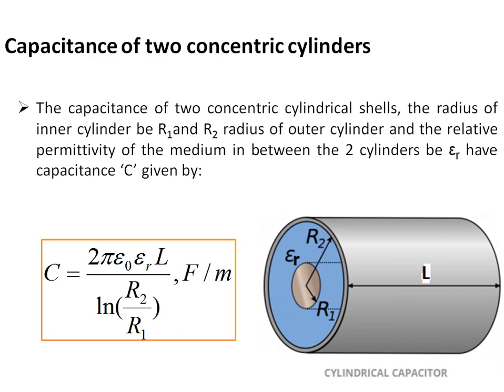In industrial capacitance probes, a concentric cylinder configuration is generally used. The capacitance of two concentric cylinders is given by C = 2π·ε₀·εᵣ·L / ln(r₂/r₁), where L is the overlapping length of the two electrodes, r₂ is the inner radius of the outer cylinder, and r₁ is the outer radius of the inner cylinder. This formula is used for capacitance type liquid measurement sensors.